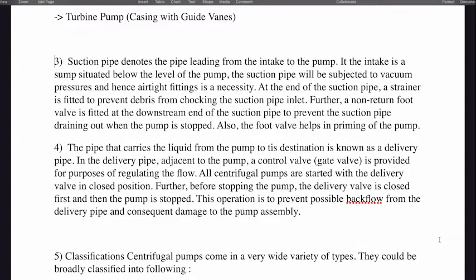The suction pipe is the pipe leading from the intake to the pump. The intake is a sump situated below the level of the pump. The suction pipe will be subjected to vacuum pressure and hence air-tight fitting is a necessity. At the end of the suction pipe, a strainer is fitted to prevent debris from choking the inlet. Further, a non-return foot valve is fitted at the downstream end of the suction pipe to prevent draining when the pump is stopped, and it also helps in priming of the pump.